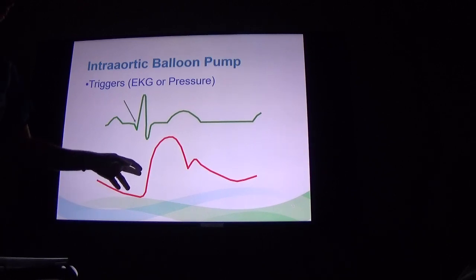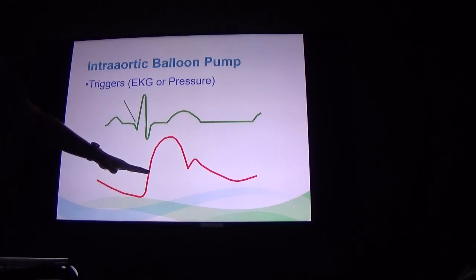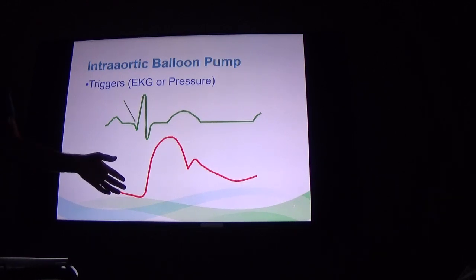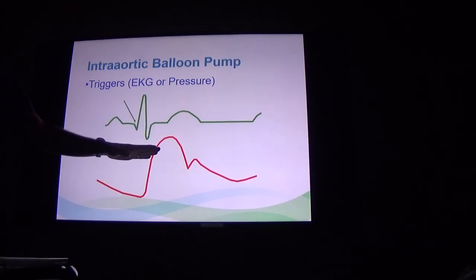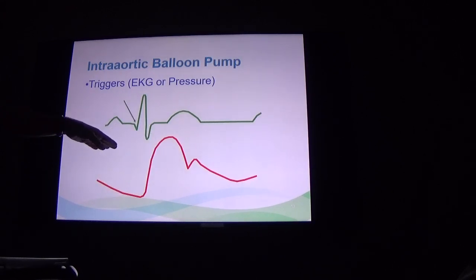Because again, the balloon will trigger off its backup, the arterial waveform. So if one of the leads pops off, it's not the end of the world. Just figure out where the lead popped off and put it back on, and the machine will go to its backup mode of using the arterial waveform.